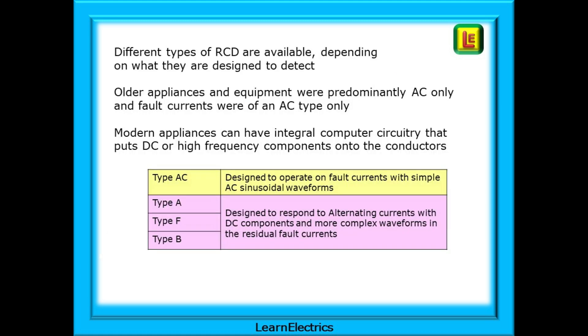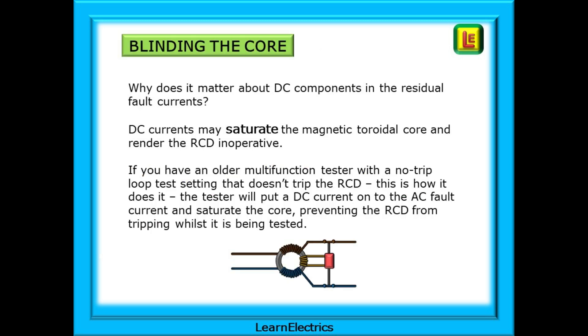Different types of RCD are available depending on what they are designed to detect. Older appliances were predominantly AC only, and fault currents were of an AC type only. But modern appliances can have built-in computer circuitry that puts DC or high-frequency components onto the conductors. The older type AC device is ideally suited to circuits with only smooth sinusoidal AC fault currents, while types A, F, and B are for circuits where modern equipment can overlay DC and high-frequency components onto any fault currents. DC components matter because they can saturate the magnetic toroidal core — known as blinding — and render the RCD inoperative, meaning it may not operate during a genuine fault.